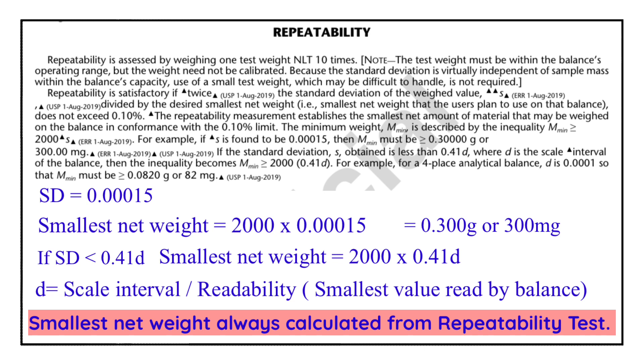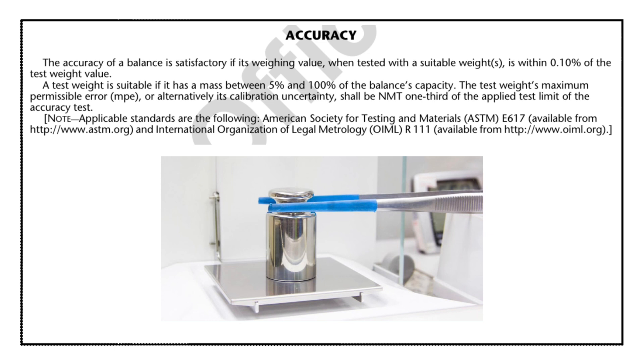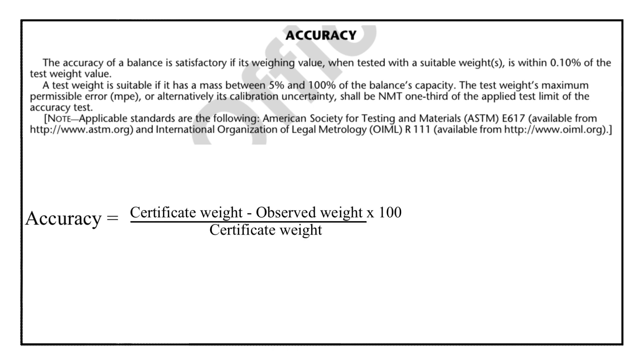Now comes the second test parameter mentioned in USP Journal Chapter number 41, and that is accuracy. To perform the accuracy test, a single test weight is selected and its weight is measured. Accuracy is then calculated with the formula: (certificate weight − observed weight) ÷ certificate weight × 100. The obtained value should not be more than ±0.10 percent.